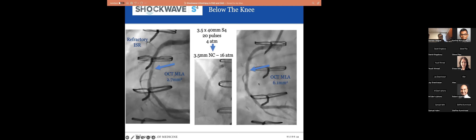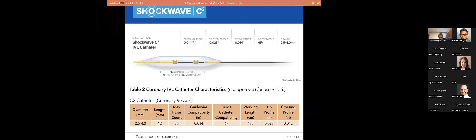So this is finally the last catheter, the C2 catheter, the coronary specific catheter, 2 in the title for 2 emitters here. And I think it's important to remember where in the balloon these emitters are, because this balloon is only 12 millimeters and a lot of the complex cases that we use this for have really long lesions. It's important that we understand where the emitters are so that we can really focus that energy as much as possible on the lesion of interest and not waste pulses again on surrounding tissue. It gives you 80 pulses. Like I said, it's 6 French compatible. Its working length is 138 centimeters. And you can see the tip profiles there, the crossing profiles there.